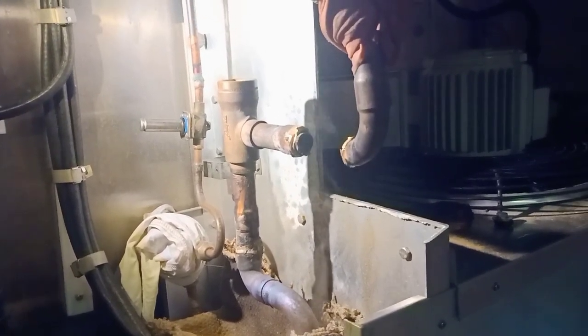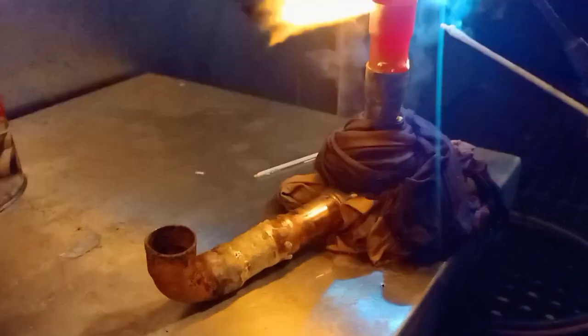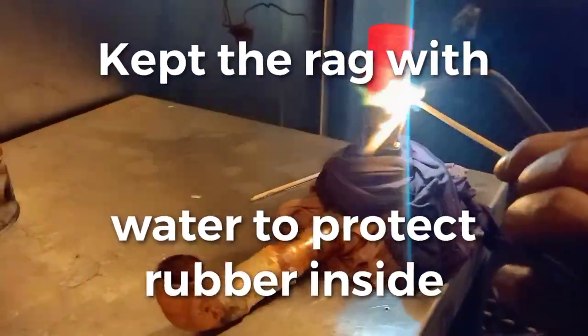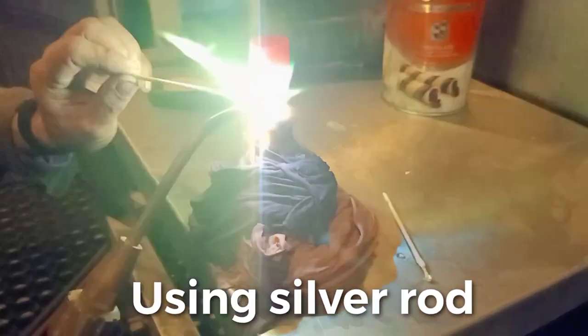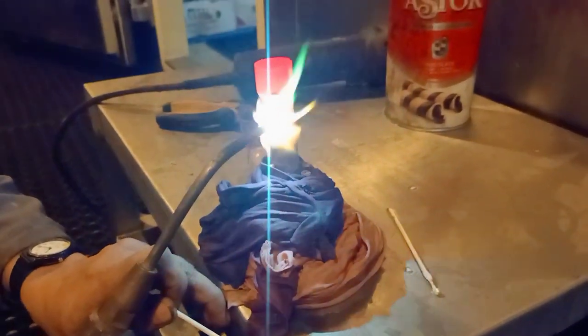Back to compressor — this is our low-pressure pipe. This is the non-return valve. We braze. Keep the wet rag to keep the rubber inside the non-return valve protected. Just using our silver rod to continue, to make sure we do not encounter any leaks. It must be 100% fitted in this cover job.